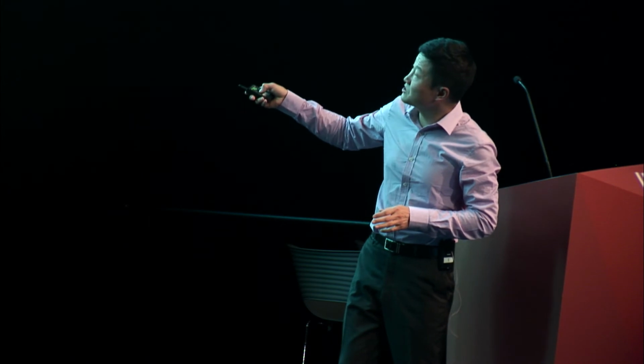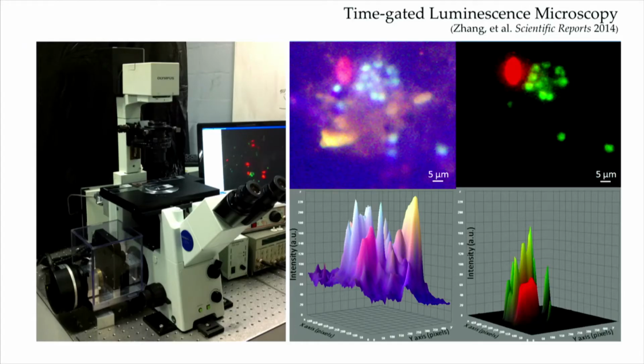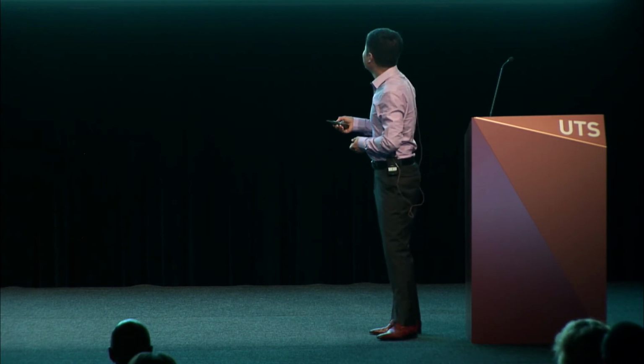But after the excitation light, the chopper blade moves away, and then the short fluorescent material disappears immediately, and then the long lifetime material will stay in the picture. So this simple technology, again, allowed you to directly see the single cell without any background. Okay? So you can further apply this technique to multiple colors, the lifetime and the color. And you can simultaneously detect Giardia, and you can also count how many cryptosporidium from the green label. So by this way, you have simultaneous high throughput detection, multiple analytes in one image.